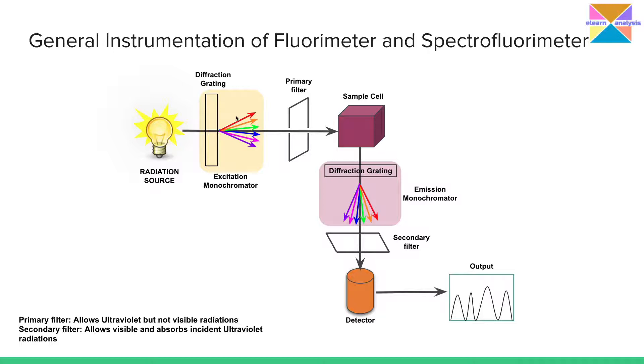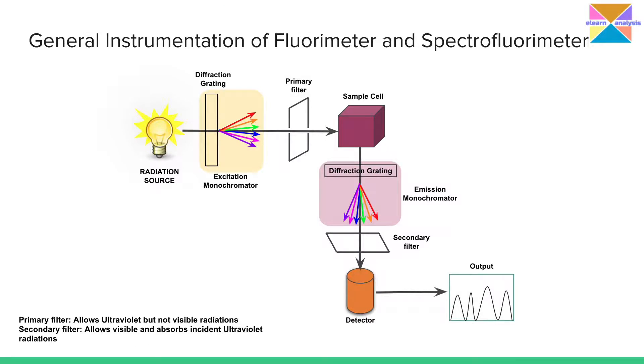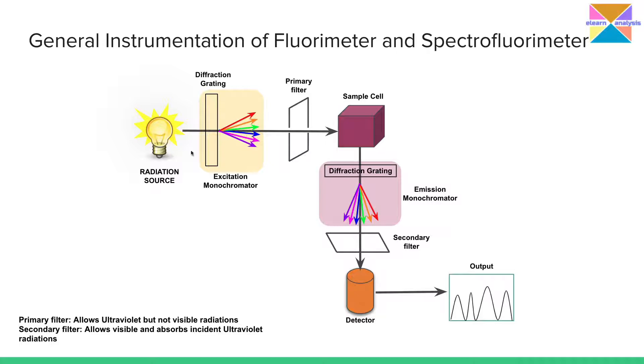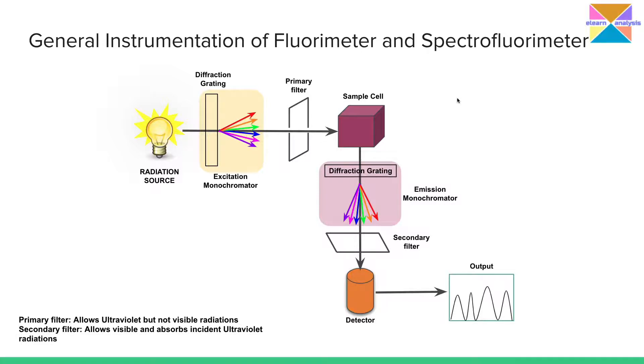The excitation monochromator selects wavelengths in the ultraviolet region, from 200 to 400 nanometers. Once those shorter wavelength radiations are isolated, they fall on the sample, which becomes excited and shows fluorescence. One important feature is that the source of radiation and the detector are arranged at right angles — unlike UV-visible spectroscopy where they are in a straight line. This is done to exclude transmitted radiation and measure only the emitted radiation.